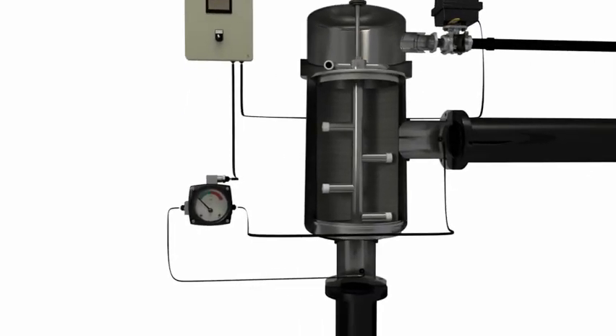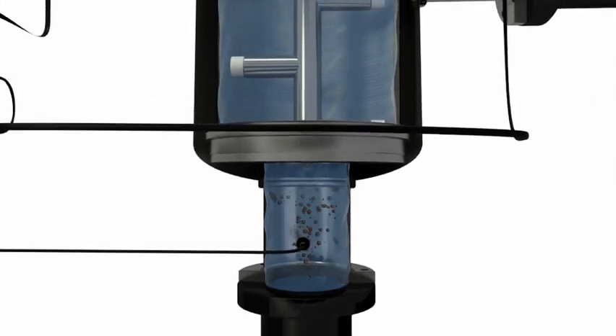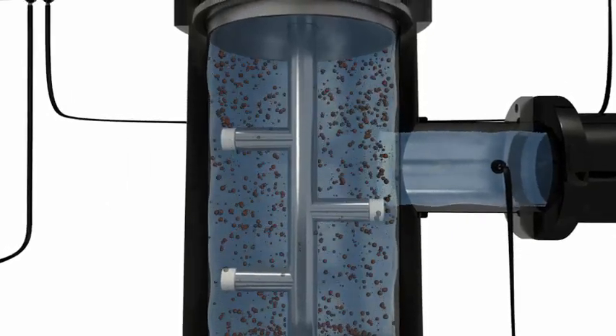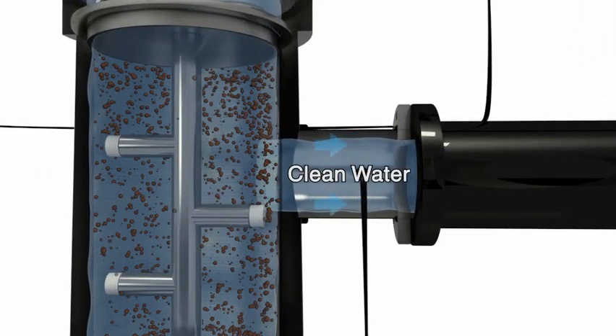During normal operation, water enters the filter through the inlet flange, moves up the center of the filter, and passes through the fine screen. Debris collects on the inside of the screen, ensuring that only clean water exits the filter.